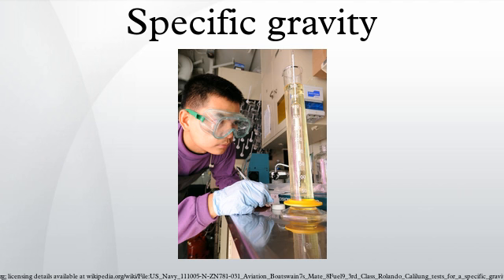Digital density meters, hydrostatic pressure-based instruments. This technology relies upon Pascal's principle, which states that the pressure difference between 2 points within a vertical column of fluid is dependent upon the vertical distance between the 2 points, the density of the fluid and the gravitational force. This technology is often used for tank gauging applications as a convenient means of liquid level and density measure. Vibrating element transducers. This type of instrument requires a vibrating element to be placed in contact with the fluid of interest. The resonant frequency of the element is measured and is related to the density of the fluid by a characterization that is dependent upon the design of the element.